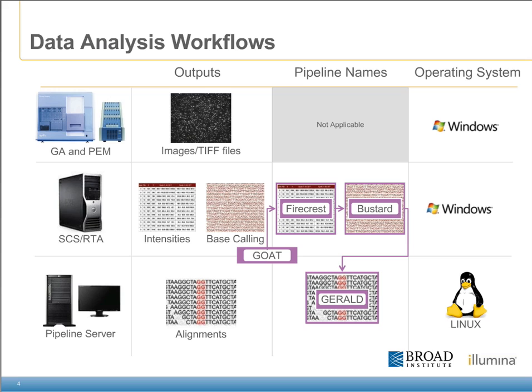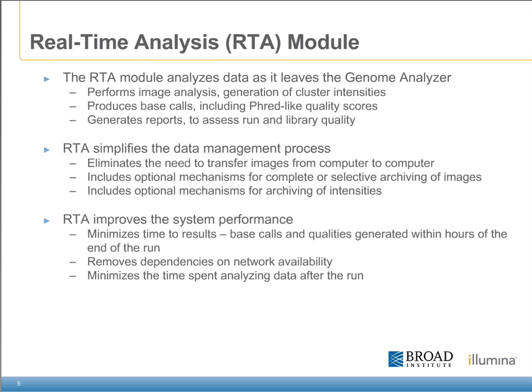The pipeline server package produces an output of alignments. This is currently available only for a Linux operating system. The real-time analysis module resides on the GA's attached PC and performs primary image analysis as well as generation of cluster intensities. Based on the resulting data, both base calls and Phred-like quality scores are assigned. RTA vastly improves the data management process as the primary analysis is done during the run in order to front-load a lot of the analysis tasks.